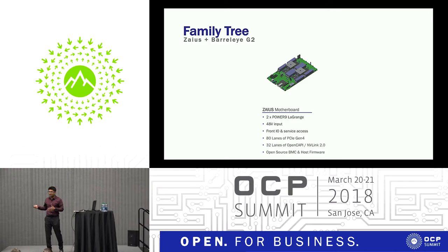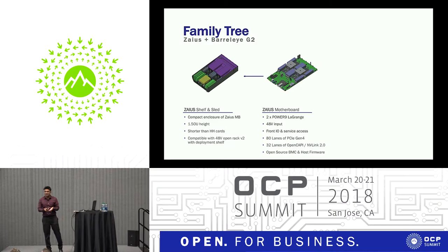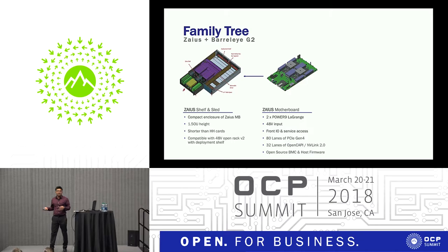On the left here, you have the Zaius tray, which is a compact enclosure around the Zaius motherboard. It's basically 1.5 OU tall, so you can't fit standard half-height, half-length cards, but you can fit some that are shorter than that. It's compatible with 48 volts OpenRack V2, but you'll need a deployment shelf to put around the server, essentially, so that it'll fit in the standard rack.